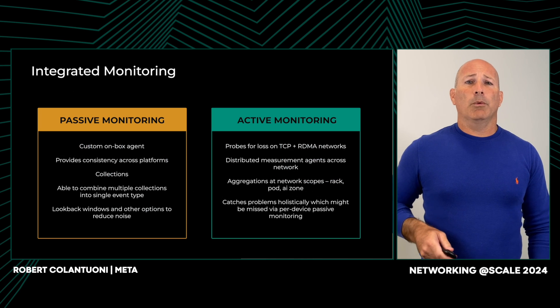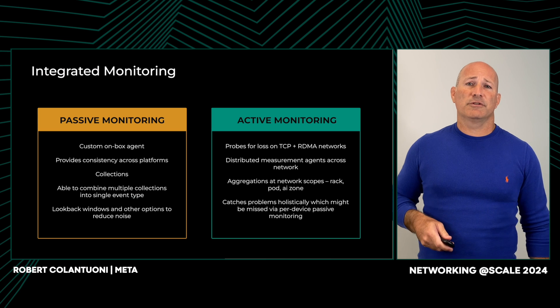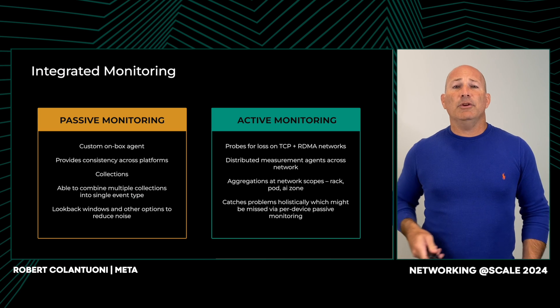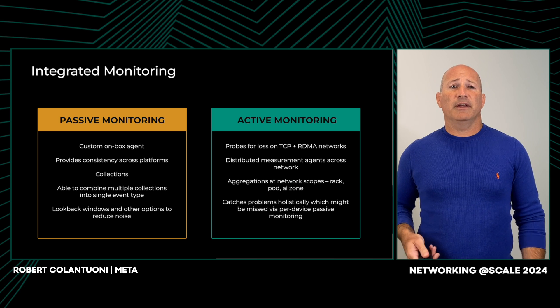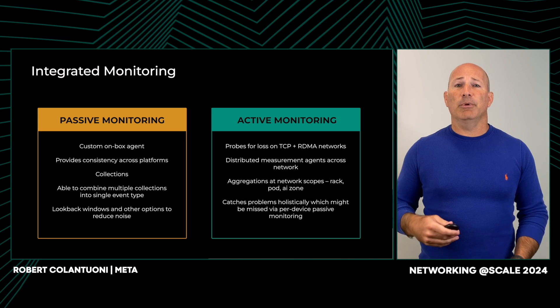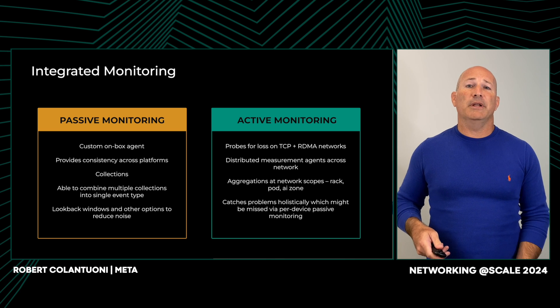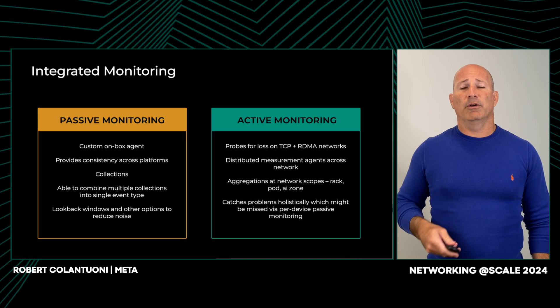Let's talk about integrated monitoring at the data center space at Meta. Passive monitoring is a traditional approach in instrumentation — this involves detecting, triaging, and alarming based on events and counters on box. The sources include SNMP, vendor-specific counters, log patterns, and custom commands. We run a heterogeneous network, meaning we have a mix of both Meta-designed and vendor-specific hardware platforms, which can cause fragmentation in our detection strategy. To address this, we have a custom agent that unifies our approach to traditional monitoring. Data collection occurs on the device and is ingested centrally, facilitating aggregate alerting and real-time trending. This on-box agent enhances monitoring by enabling combinatorial detections and look-back windows, significantly reducing noise — for example, indicating a line card failure instead of triggering multiple alerts for each port and protocol event.